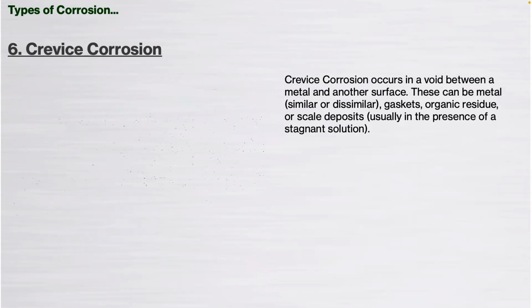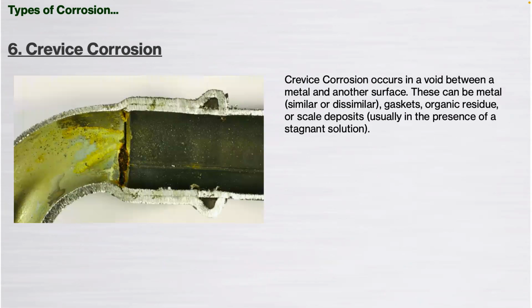Crevice corrosion. This photograph here is actually a lot of the press fit, sort of common, very popular now is the rise of press fit pipework, crimped pipework. This is mild steel, thin-walled mild steel. So you can see, well, you may not tell, but it has a rubber seal which has been crimped. Now, no issue with the installation. I think it's more a manufacturing defect.